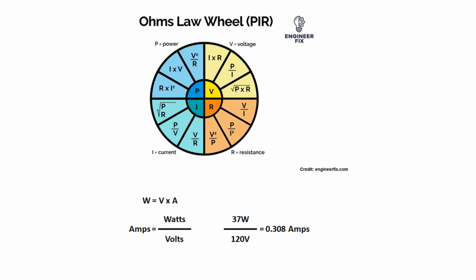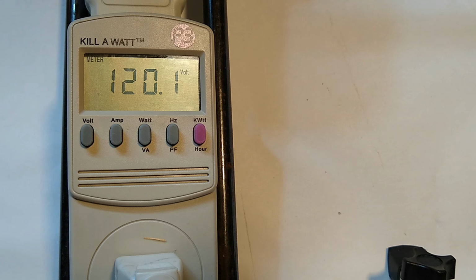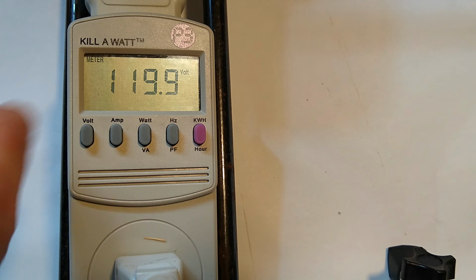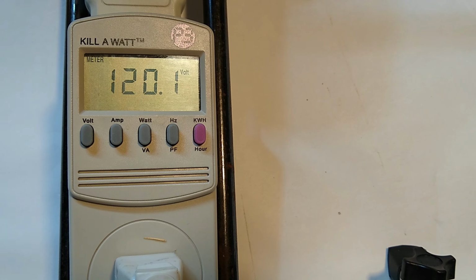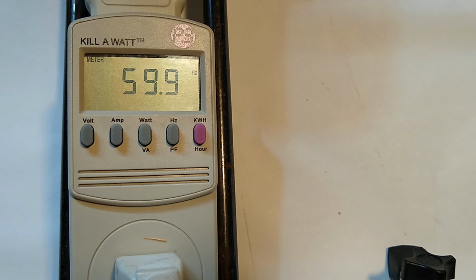Wrong. Why did I say that's wrong? Did you catch my intentional mistake? Let's take some current measurements on the running duct booster and we'll learn why that's wrong. So I'm doing my duct booster electrical measurements using a Kill A Watt meter. The power source for these measurements is just a cellar wall receptacle. Voltage is 120 volts AC, and frequency is 59.9 Hertz.